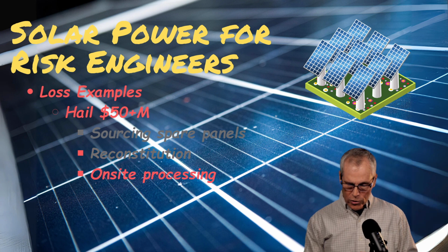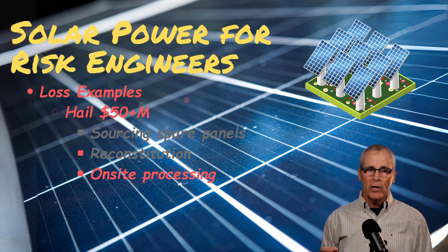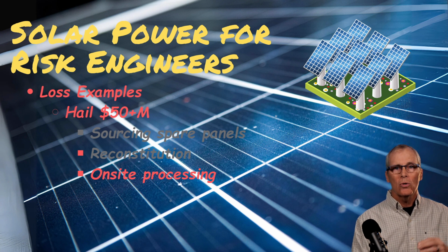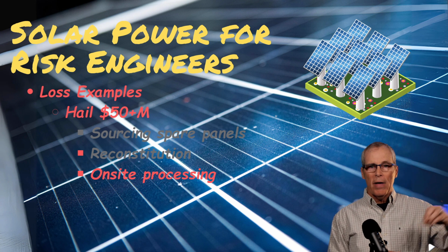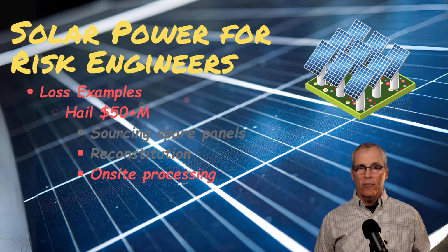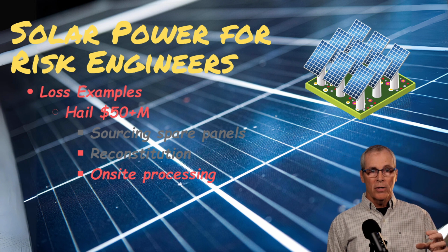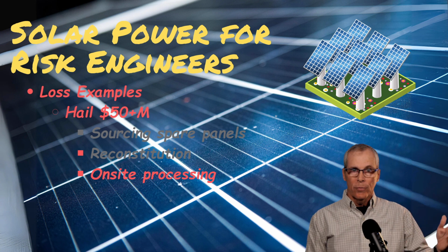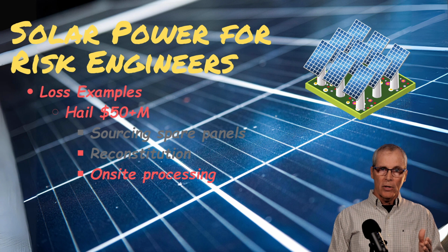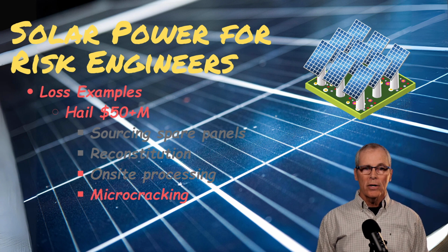On-site processing, like we just covered, is when we can do that testing on-site and not have to send these things off-site. Because by the time you send a module to a manufacturing site to be EL tested and then receive it back, you could have bought a new module. And everybody knows that. So this whole concept of the testing cost has to be controlled and limited. It can get out of hand to the point where you're basically into a replacement cost just because of testing. So bringing a testing van on site really helped us there.